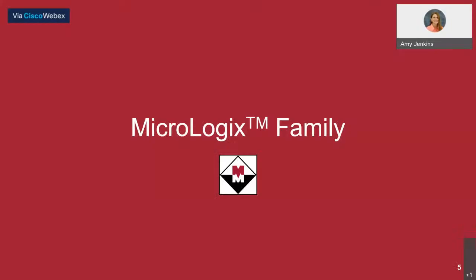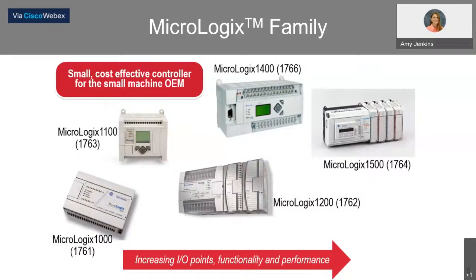Now let's focus on the MicroLogix family. The MicroLogix 1000 was the first to be released in 1994, and it's displayed in the lower left-hand corner. This small and inexpensive controller opened the door for using RSLogix 500-based programs on smaller applications that previously were not cost-effective with the SLC 500 family. The catalog number for the MicroLogix 1000 starts with a 1761. It only offers embedded I/O, and it does not support any additional I/O modules.